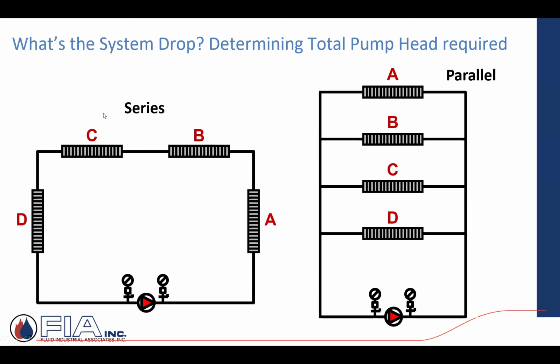Kind of an interesting drawing, and it's showing a series piping versus a parallel. And this sometimes trips people up. In this orientation, whatever the flow requirements, the BTU load is, everything, terminal units and piping, are all in series. So when you're establishing the pump head, you're accounting for everything that's in line because it's one loop. This is not that common in a fan coil application because you're going to be more in this orientation over here on the right, the parallel. But if I had, like in this room right here, baseboard, and then I go to the next room, I have more baseboard, it's in series. So I would be calculating not only the pipe diameter, but the pressure drop of these terminal units. And I'd add it all up to establish a known pressure drop.